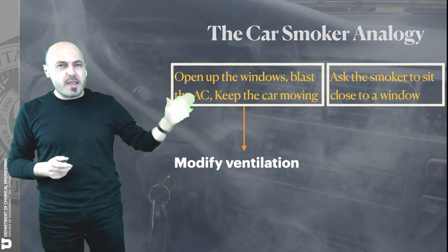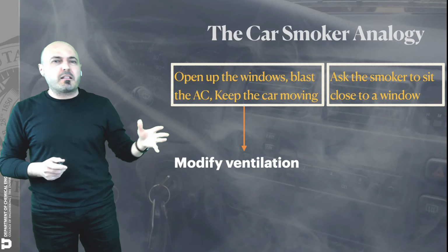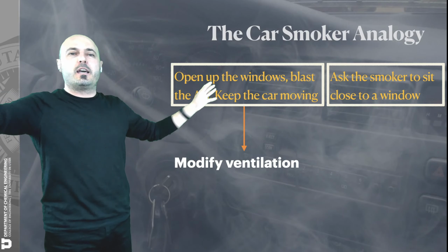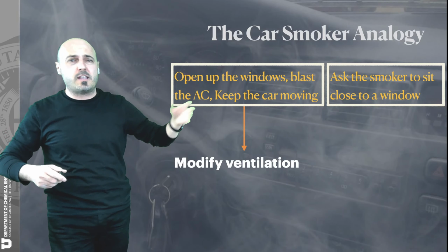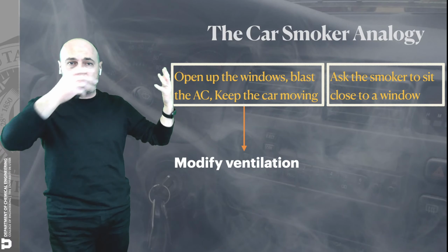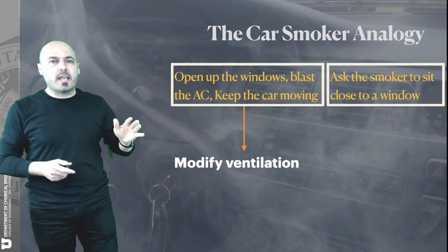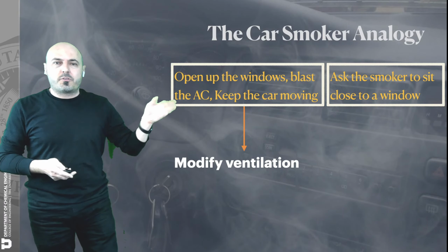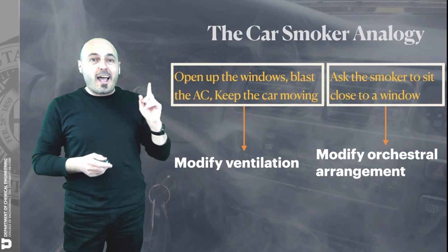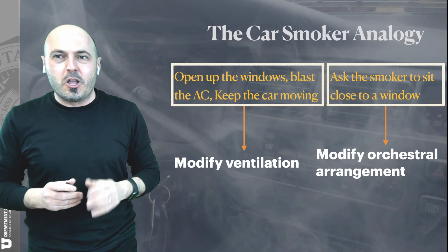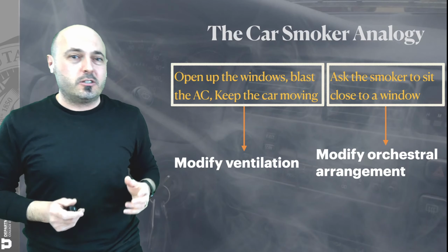I'll tell you a little bit about that. That did not have a major effect. We ended up settling on 80% return, so that 20% of the air leaves through the doors. We tried to change that to 60% return, so that 40% of the air leaves. It didn't make a big difference. So we just settled on the 80% throttling of the HVAC.